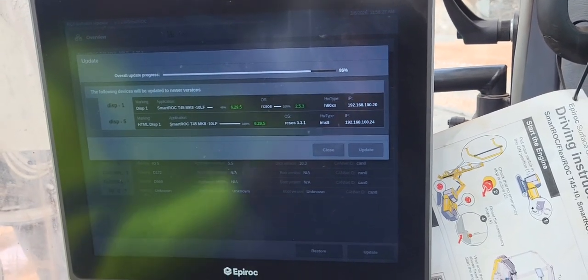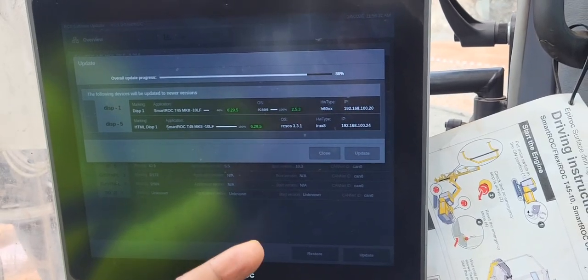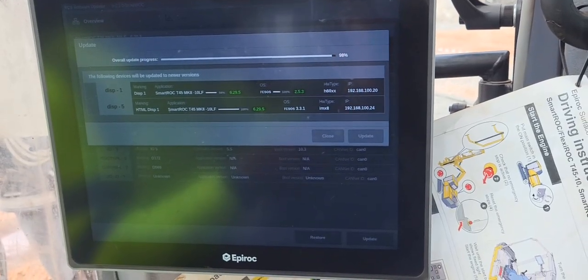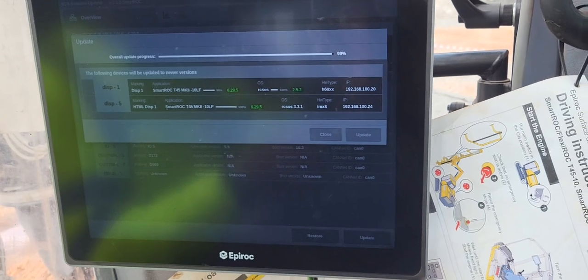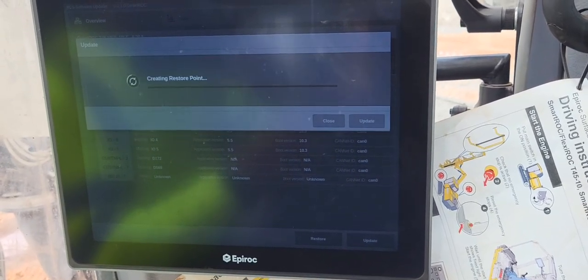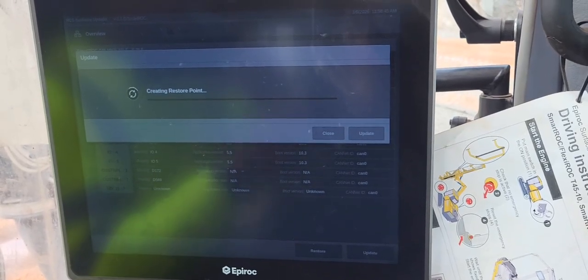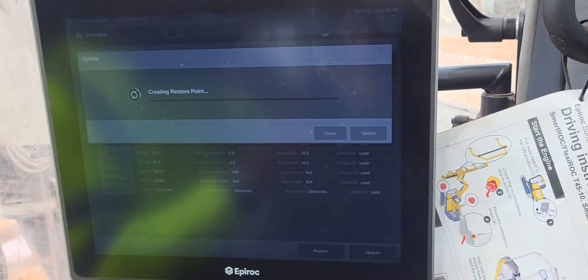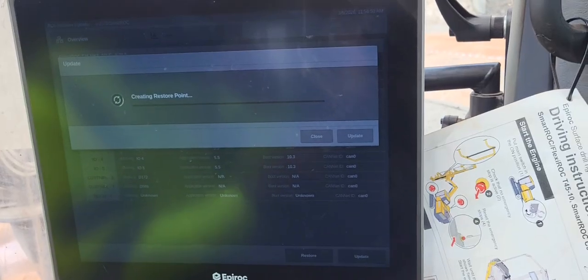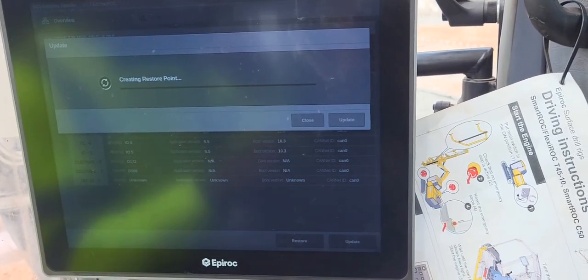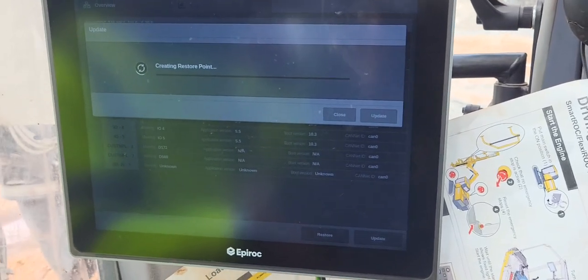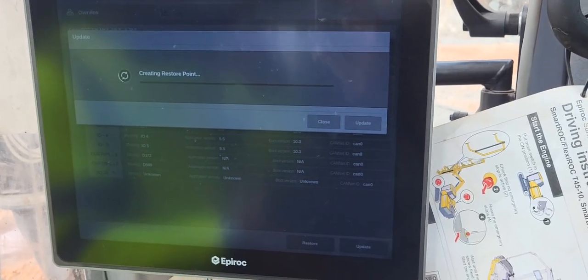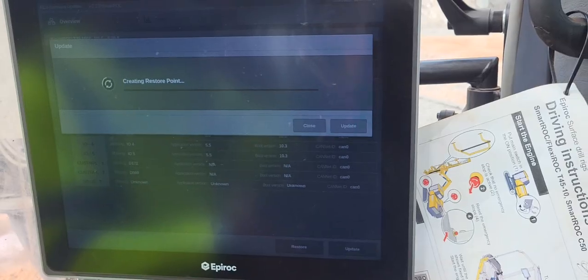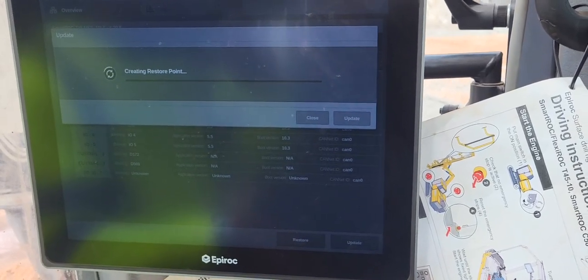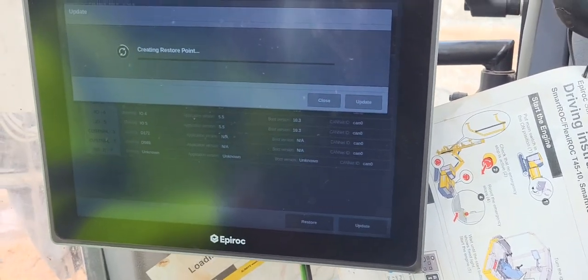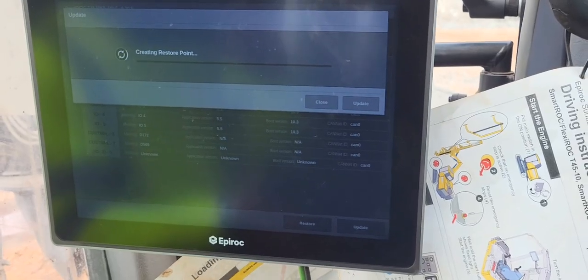So in case you forget, you see you use 2 pen drives. Yeah, I always use 2 pen drives. One with the software and one with the parameters. I never mix them. So must we always go with 2 pen drives, using one to copy? Yes. So what if you don't have two, only one? Must you use one to copy and then use a laptop? You can save before, then move it to your laptop and from your laptop. But the USB stick with the software must always be clean, only the software inside, only the software package, that is a PKG package. Because if you have something else, it can corrupt the system. So it's very important to only have the software.